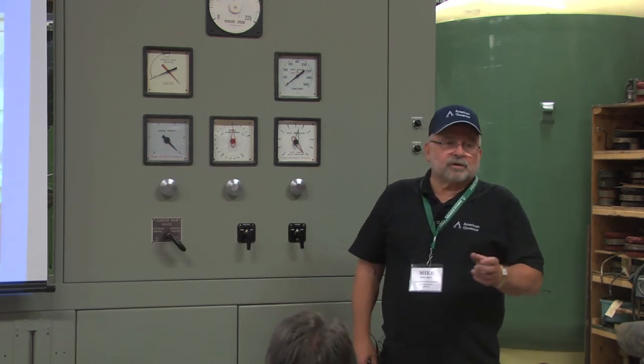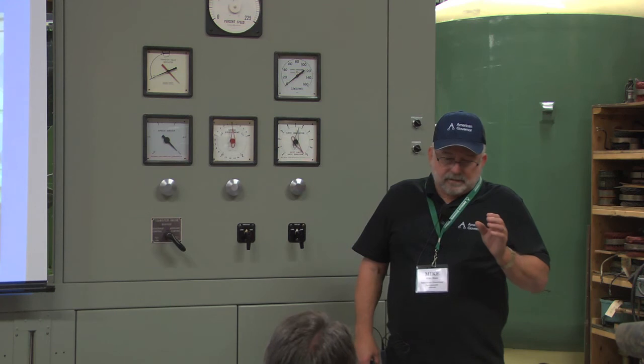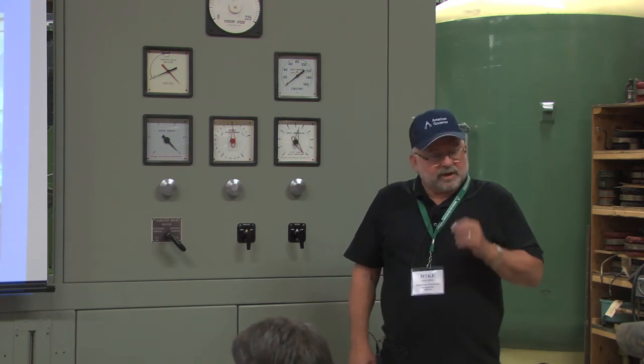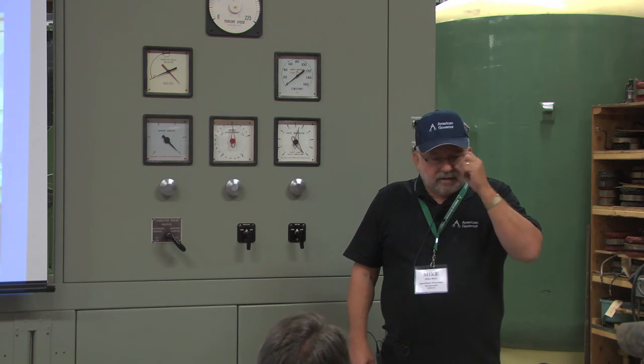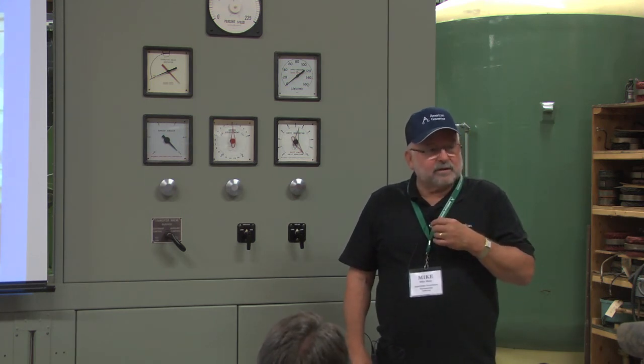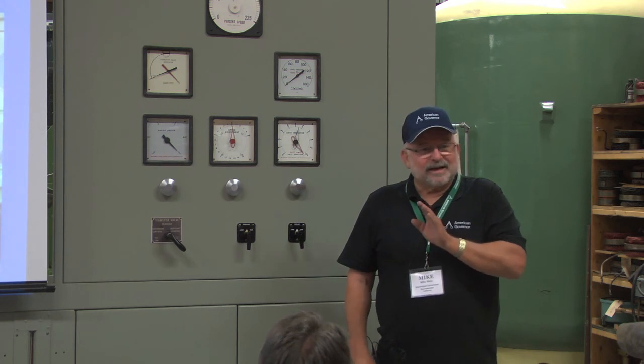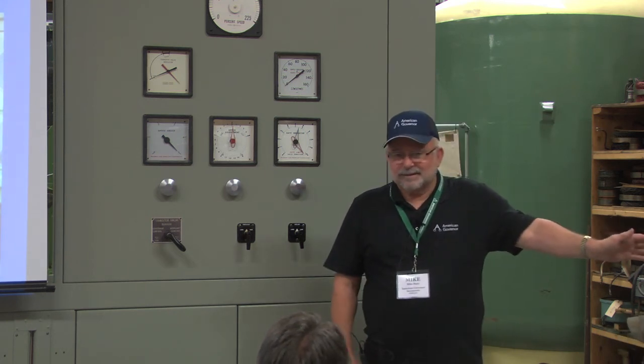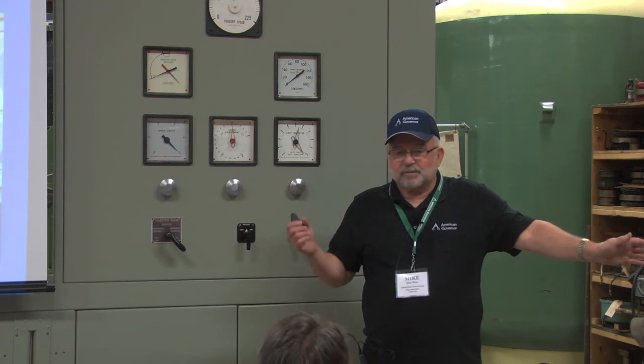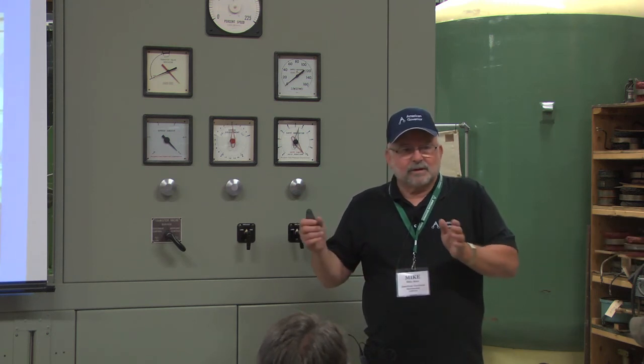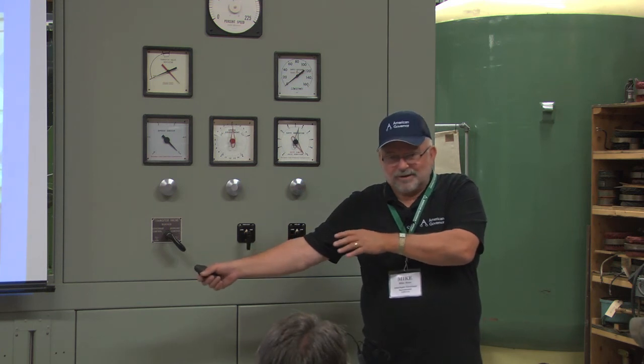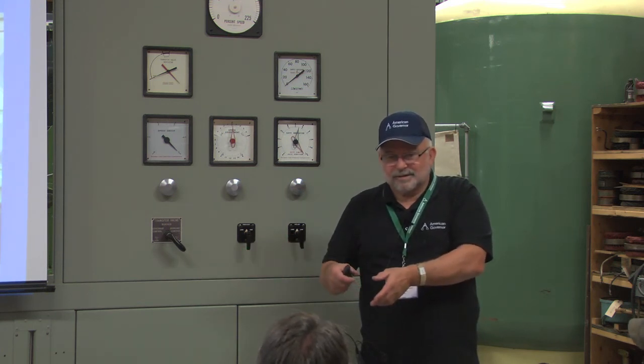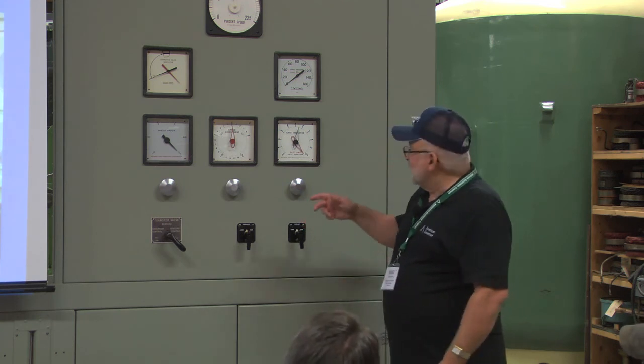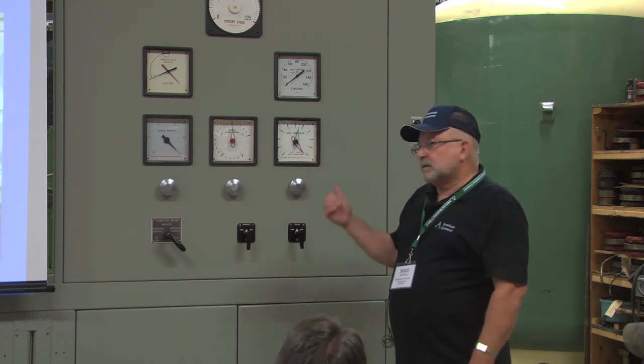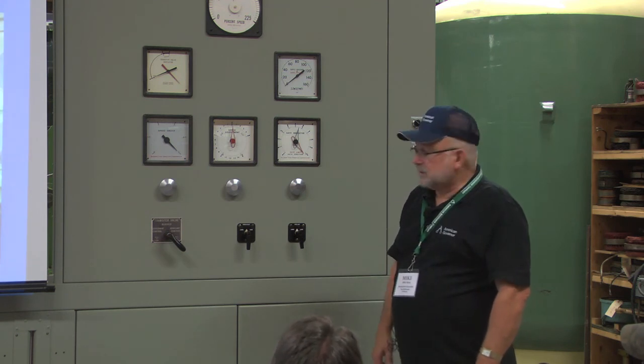You know, I went to, I believe it was for the Corps, Boysen Reservoir, and I asked him, why are you running 100% gate? And that's the big difference. I was in the utility business, he's in the water business, all right? He's got to deliver so much water down the Wind River out of that lake every day, and it goes at 100% gate. And I said, you know, you're sacrificing cavitation on that runner for delivering that water. In fact, I had to prove it to him. He says, well, yeah, but I said, I don't want to lose my megawatts. I said, you mind if I play with it a second? He says, no, go ahead.